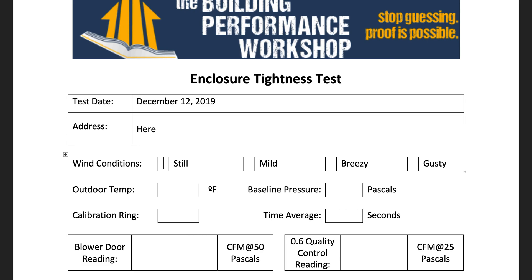You want to ideally do the test when it is still outside, and you would just put a simple little X or checkmark there. If you do a test during a gusty or very blustery day — and I have done tests where the baseline is like 37 pascals — that's not ideal. If you have already traveled 10 hours to get there, you're not going to come back tomorrow. So sometimes you have to make do, but you just want to know what was going on outside when you did this test. The temperature outside — let's say it was 50 degrees. We're in Atlanta.